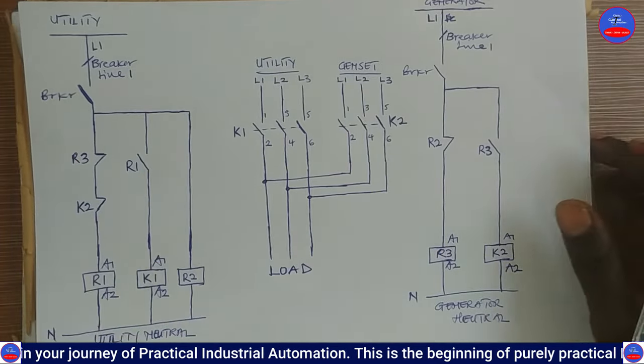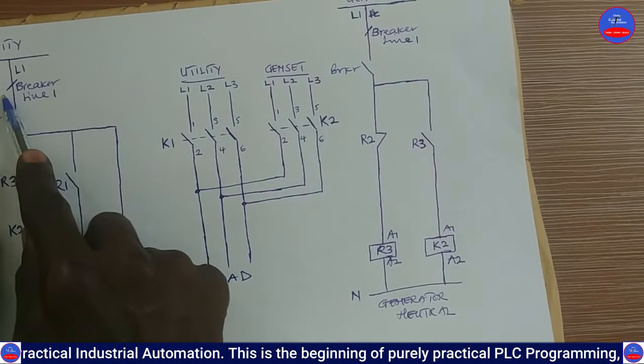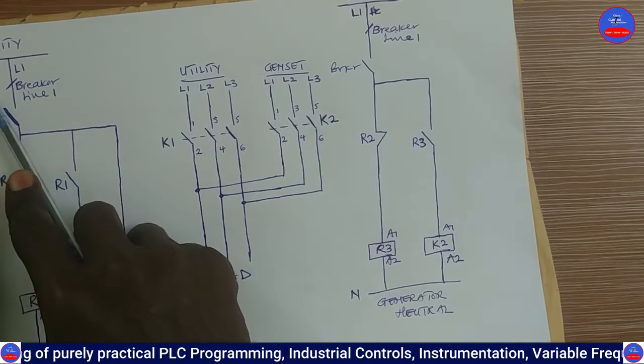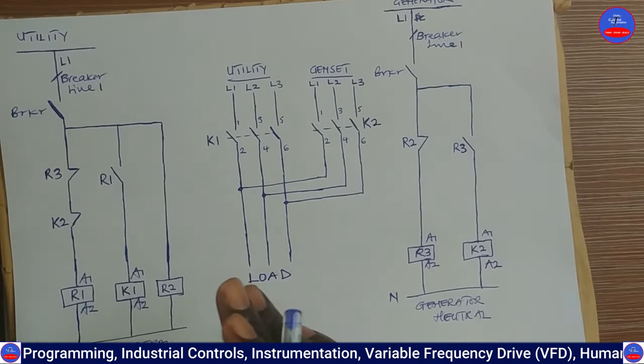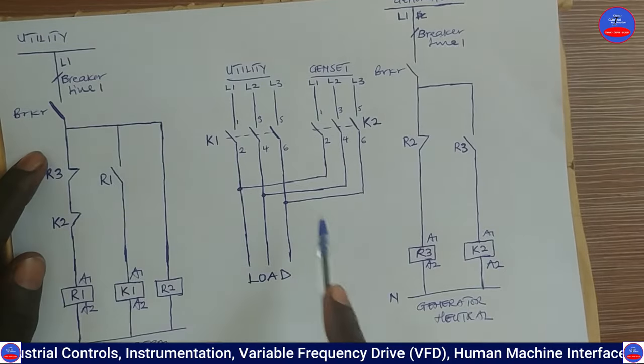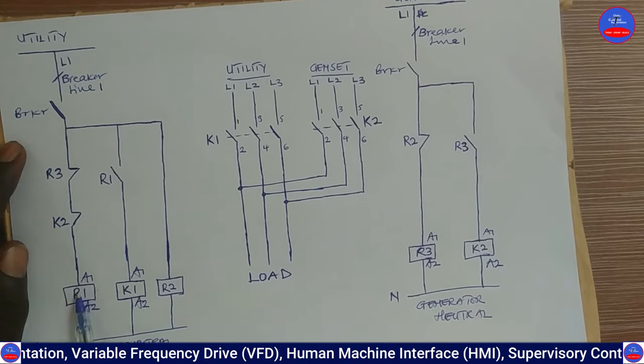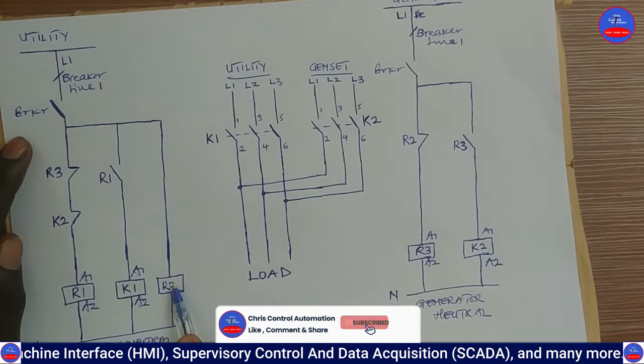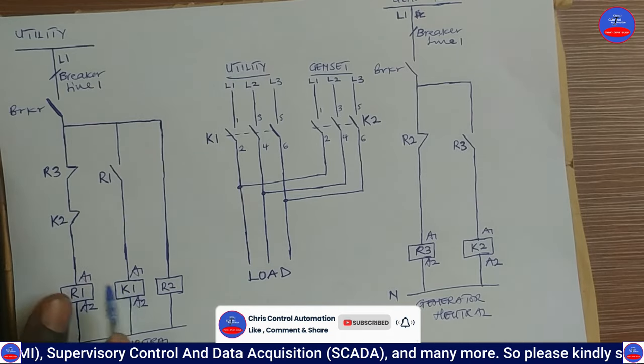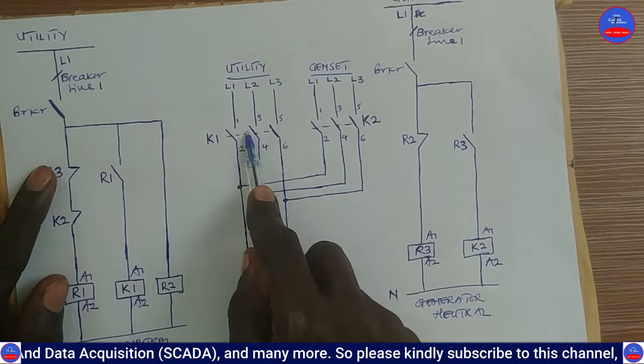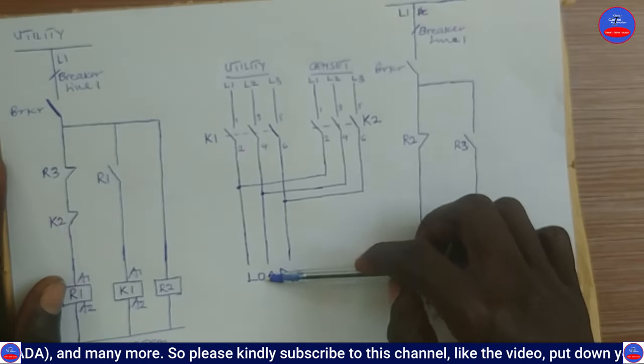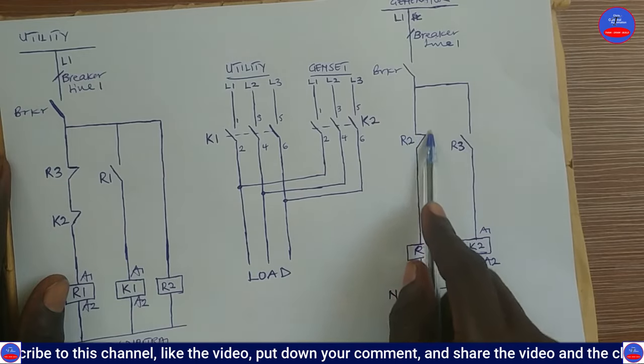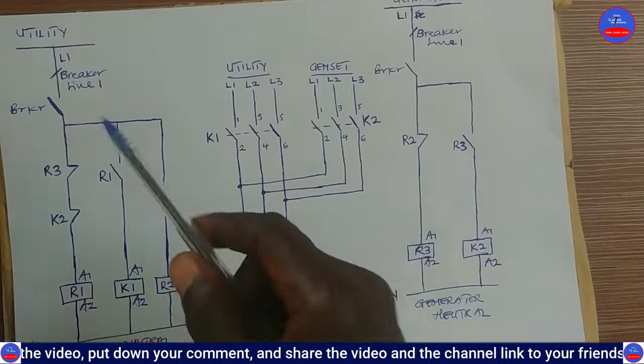Now, assuming the utility power line goes off — meaning we open this breaker — the utility power will go off. The moment it goes off, R1, K1, and R2 all de-energize. When K1 de-energizes, its contacts open and the utility power is cut off. When R2 also de-energizes, its contact closes back, ready for the generator side to operate.